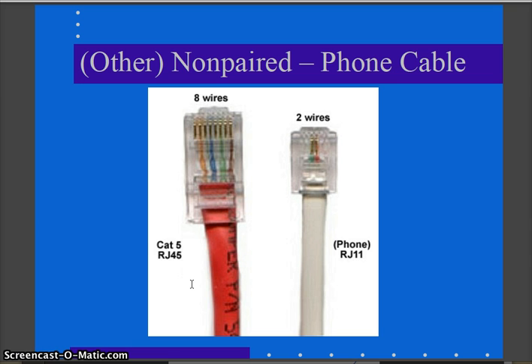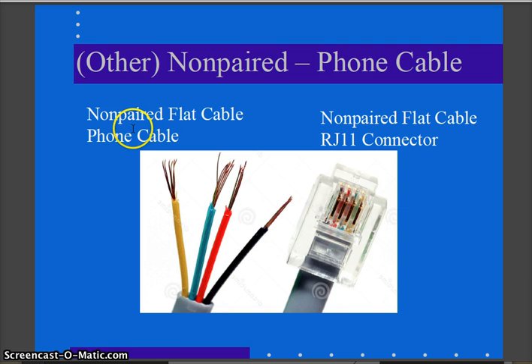Now we'll touch on non-paired or phone cable. Non-paired phone cable is typically a flat two- or four-wire cable terminating in an RJ11 jack — your standard phone connection — as opposed to the eight-wire RJ45 twisted pair, like Category 5E cable used for networks. Here's a picture of non-paired flat cable with four ordinary wires, color-coded but not twisted together, terminating in an RJ11.